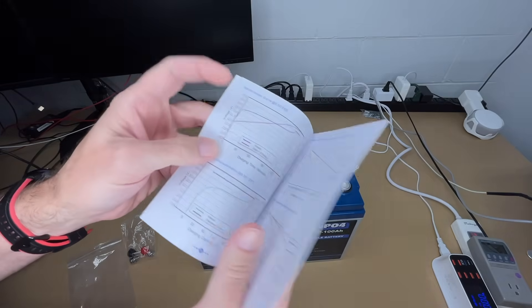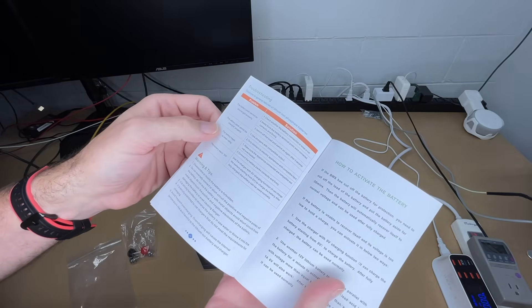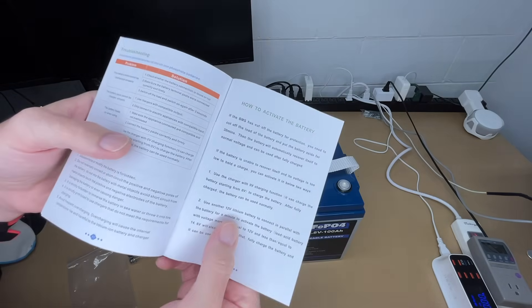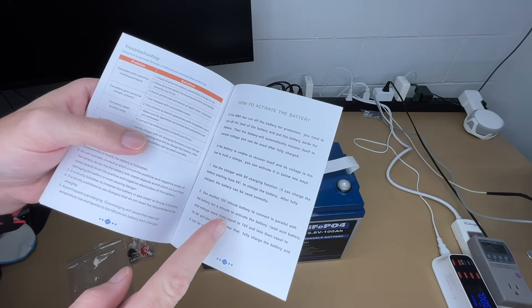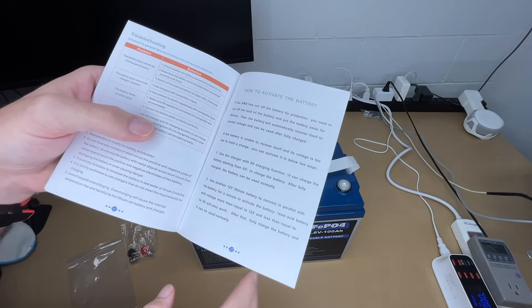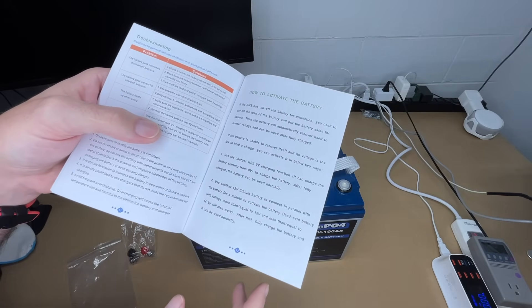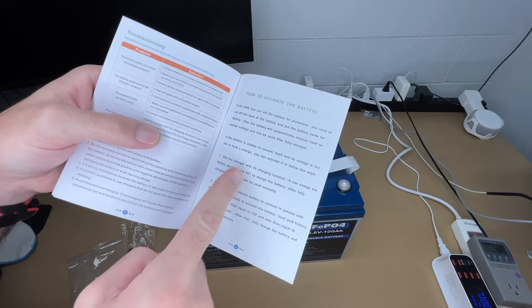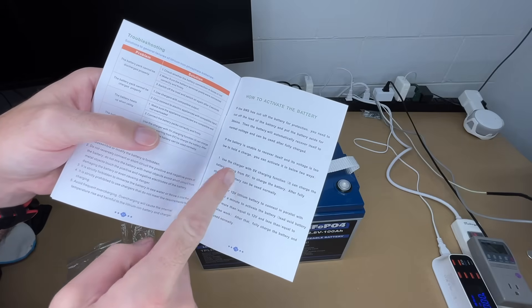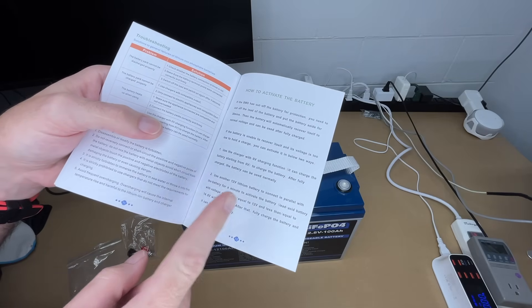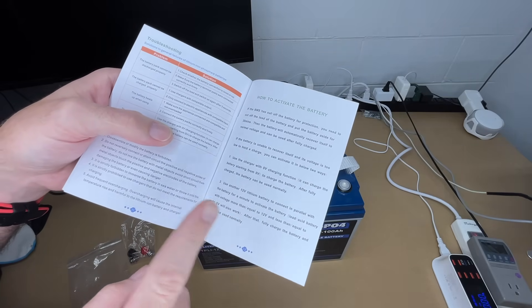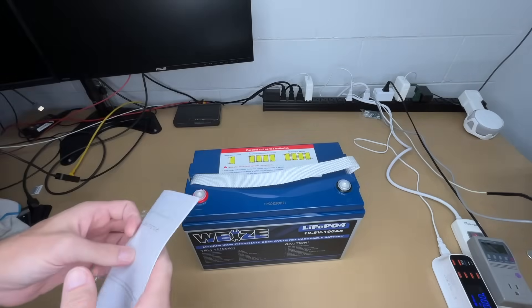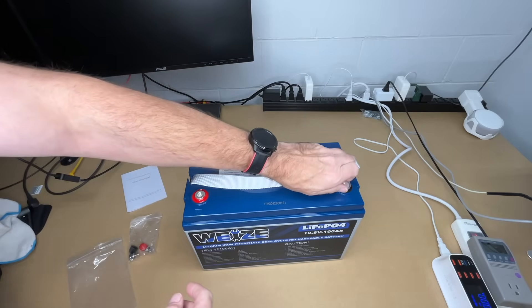Then we have some other characteristics and troubleshooting. This talks about how to activate the battery. If this has zero volts on the terminal, it doesn't mean it's necessarily bad—it might just need to be activated. You can use a charger that's able to activate it, or you can connect it in line with a lead-acid battery to turn on the BMS.